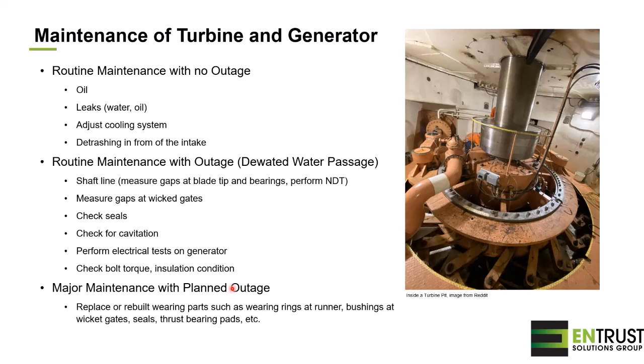We also will plan for significant maintenance on a plant outage. At that time, that requires engineering. We will replace or rebuild the wearing parts at that time, such as the wearing rings between the runner and the fixed parts. We will replace the bushings of the wicket gates. We will replace the seals, and check and confirm that the thrust bearing pads are still in good condition.